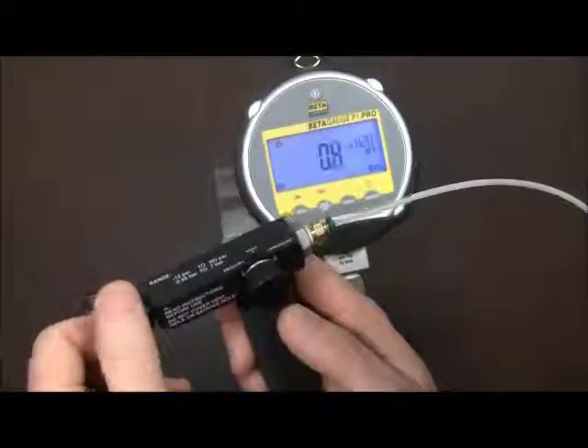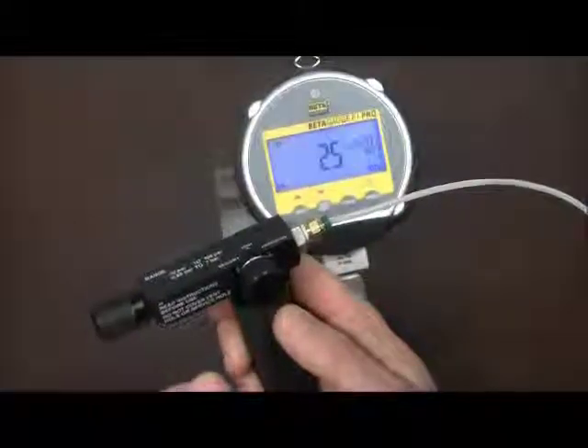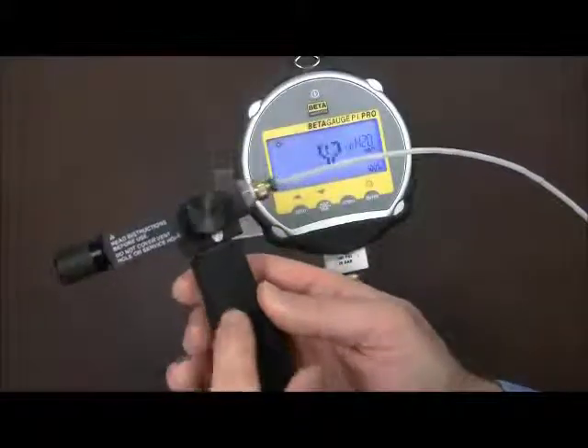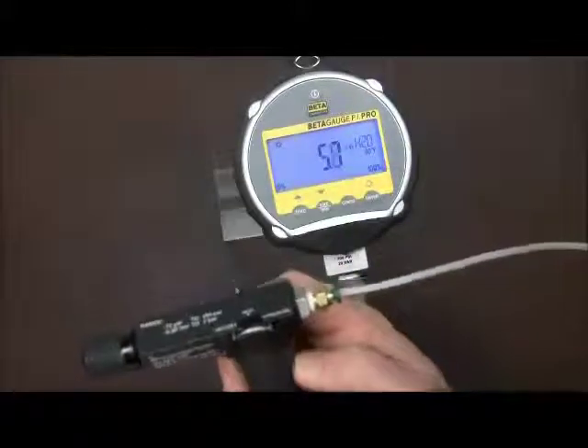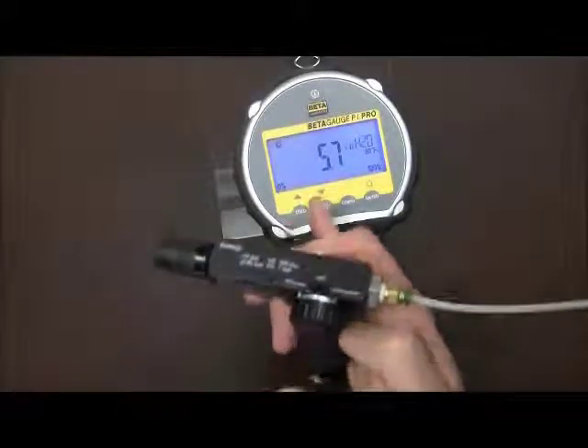We're going to use the vernier to dial in our inches of water. Both the vernier and handle are thermally isolated so we can lock in tenths of an inch of water pretty quickly.